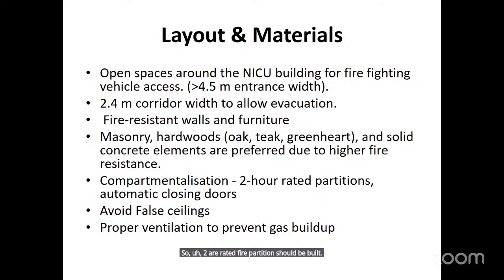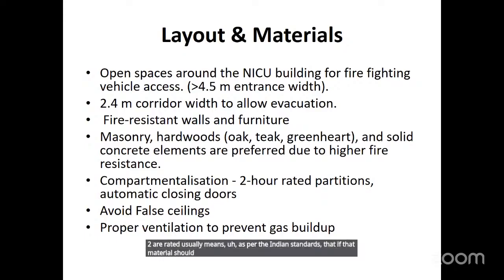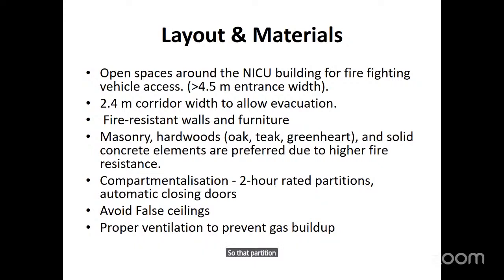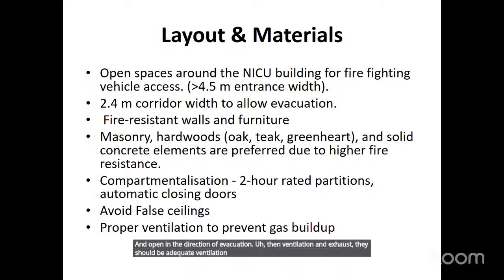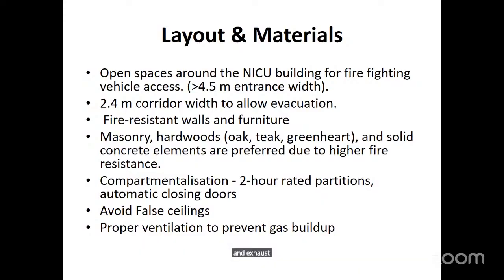2-hour rated usually means, as per the Indian standards, that if fire occurs, the material should not collapse within 120 minutes of fire. So that is the 2-hour fire rating. That partition should be 2-hour fire rated, and there should be automatic closing doors and dual escape routes. The doors must be self closing and open in the direction of evacuation. Then ventilation and exhaust: adequate ventilation should be provided to prevent accumulation of oxygen and anesthetic gases. And exhaust fans should be spark proof and maintained regularly.